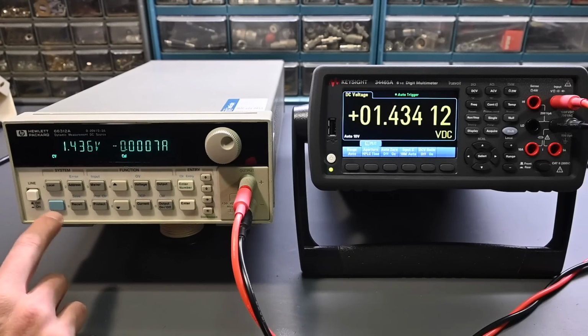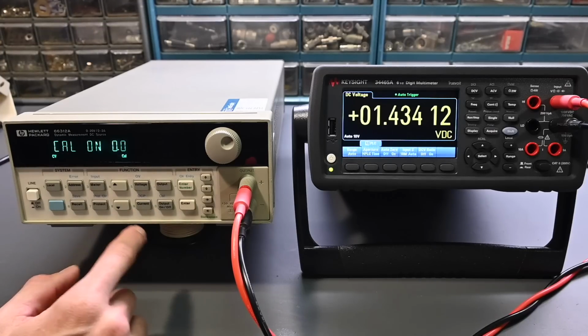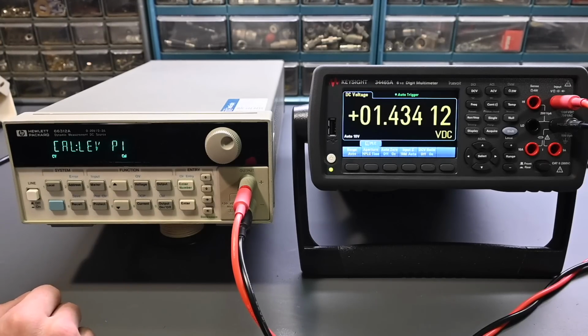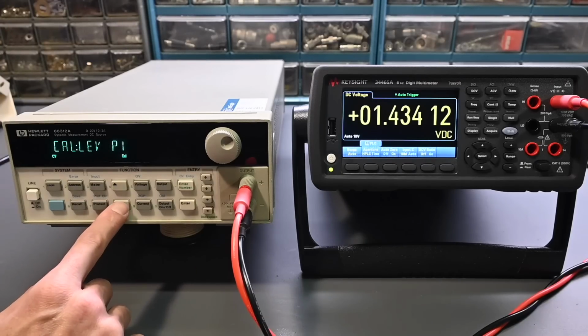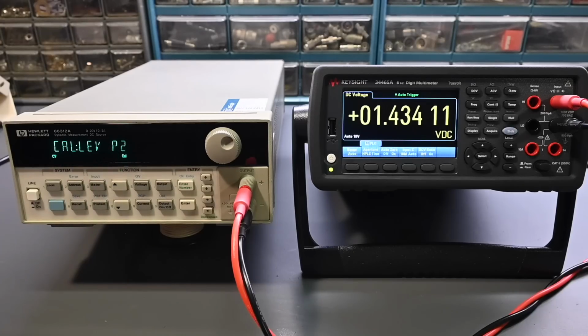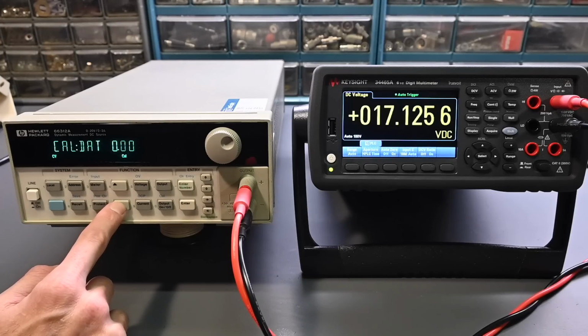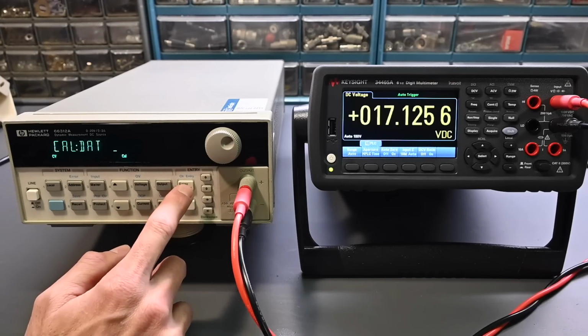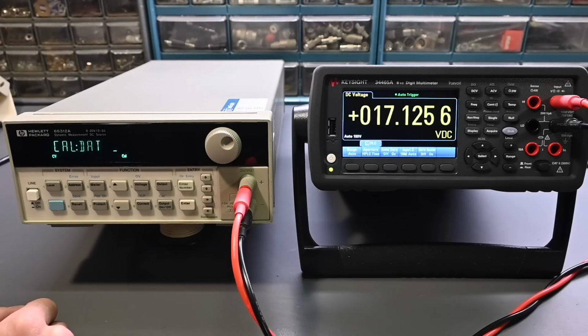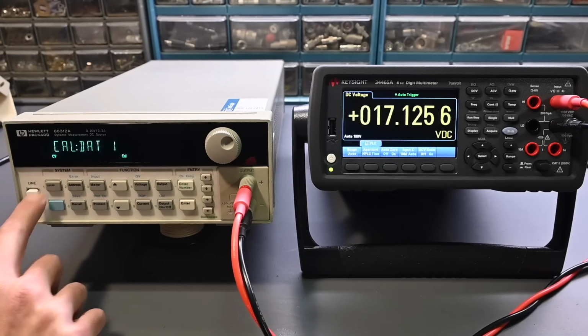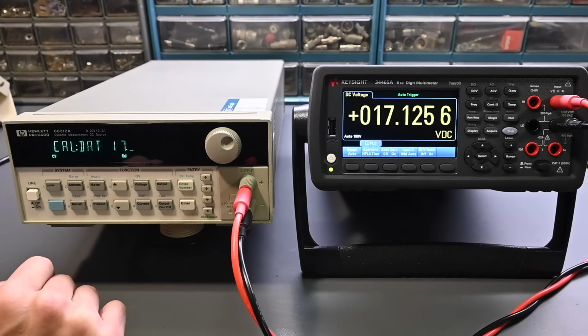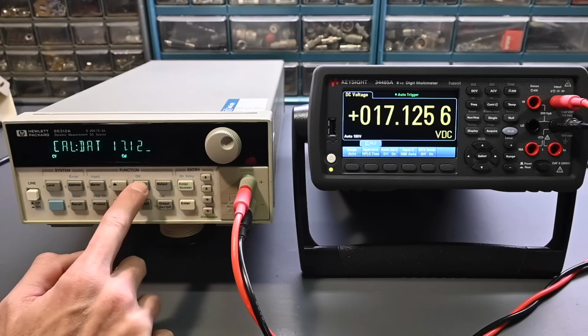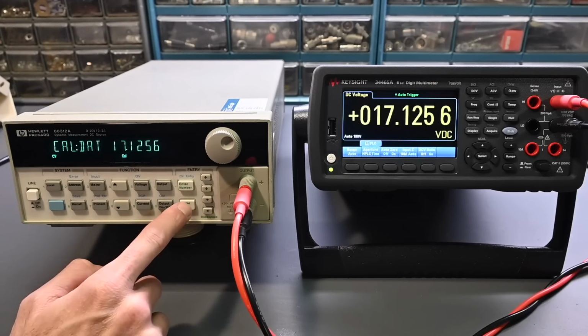It says press Shift Cal. Scroll to Cal level. Use the down arrow to scroll to P2. So it's not this arrow, it's this arrow right here. P2, the second calibration point, and press enter. It says press Shift Cal. Scroll to Cal data. Press enter number. And enter the second voltage value on the digital multimeter. So 17.1256. 1256. Enter.